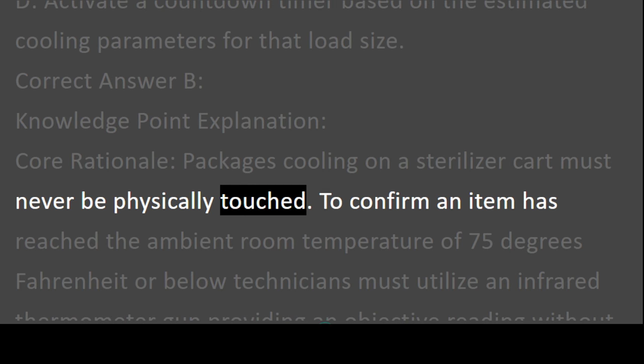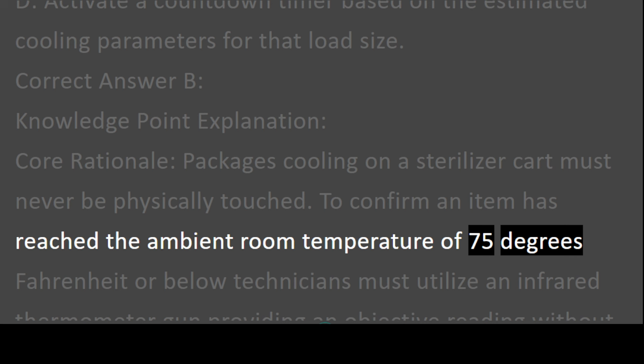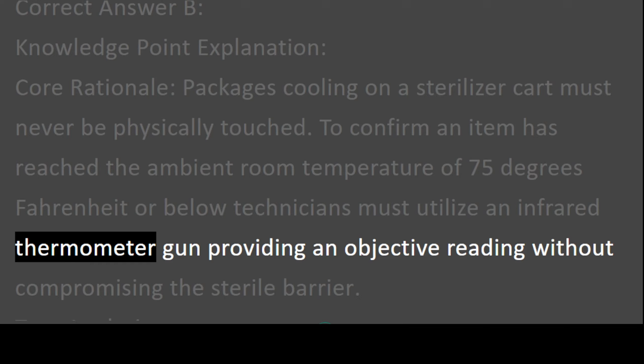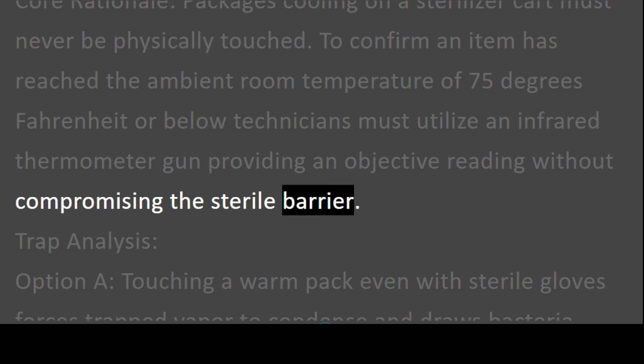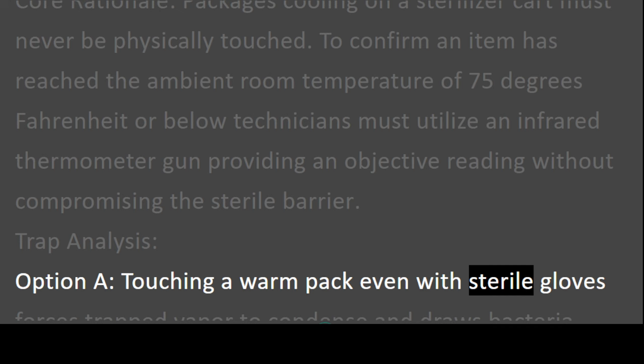Core rationale. Packages cooling on a sterilizer cart must never be physically touched. To confirm an item has reached the ambient room temperature of 75 degrees Fahrenheit or below, technicians must utilize an infrared thermometer gun providing an objective reading without compromising the sterile barrier. Trap analysis. Option A. Touching a warm pack even with sterile gloves forces trapped vapor to condense and draws bacteria through the porous wrap via wicking.